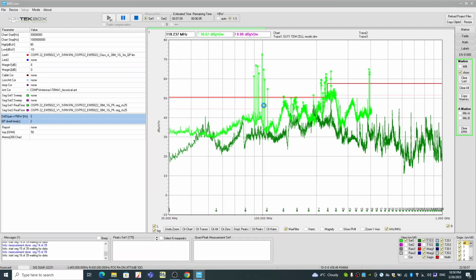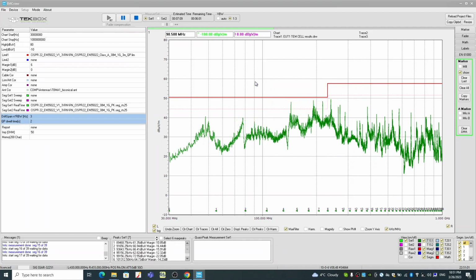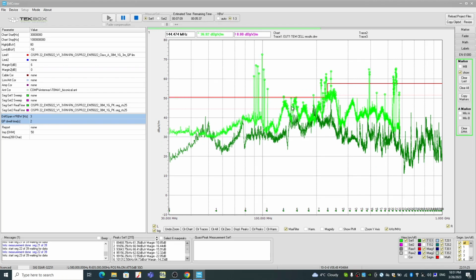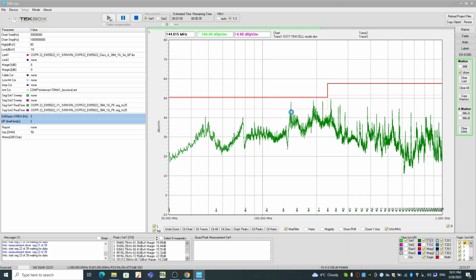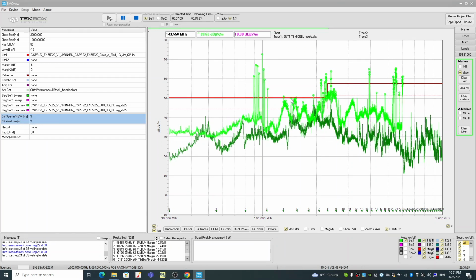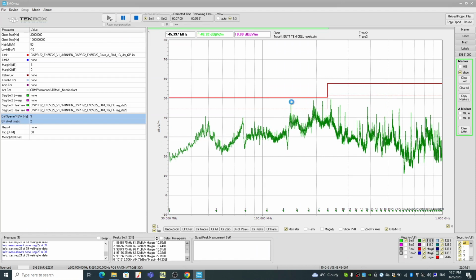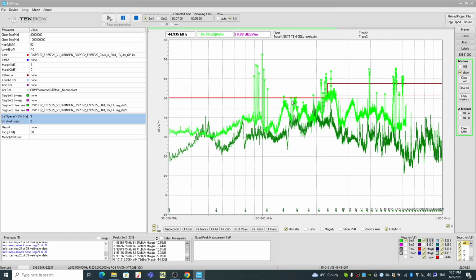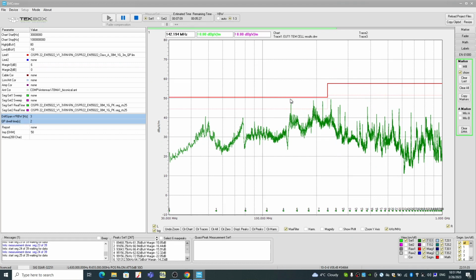For example, we know these come from radio transmitters, definitely not coming from the DUT, simply because we can't see any emissions in the TEM cell. Here we can see a spike, but in the far field it's actually quite okay. I have my eyes on this peak here, because you can see in the TEM cell we can capture it, and in the far field we can also capture it here. So that's something I need to have a closer look at.